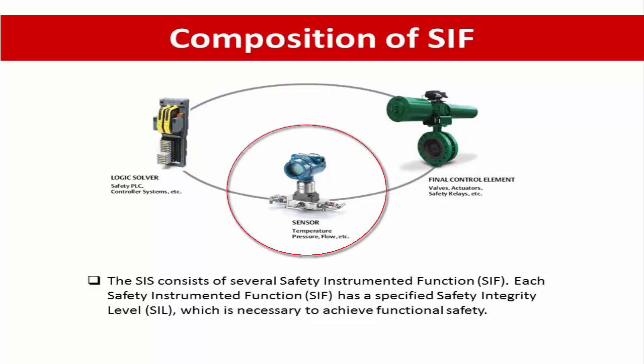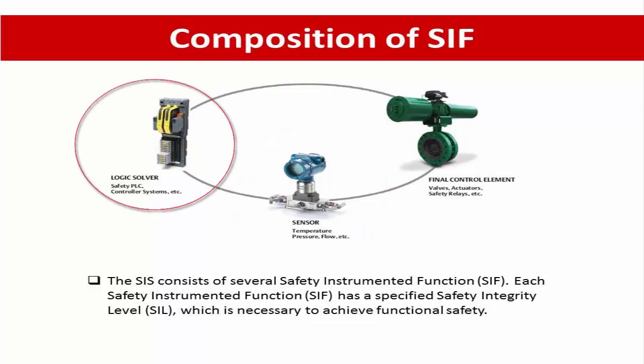A SIF is composed of three elements. The first is the sensor. Sensors are used to collect information necessary to determine if an emergency situation exists. The purpose of a sensor is to measure process parameters such as temperature, pressure, flow, level, or similar, to determine if equipment or process conditions have gone out of bounds. Sensors range from simple pneumatic or electrical switches to smart transmitters with on-board diagnostics.